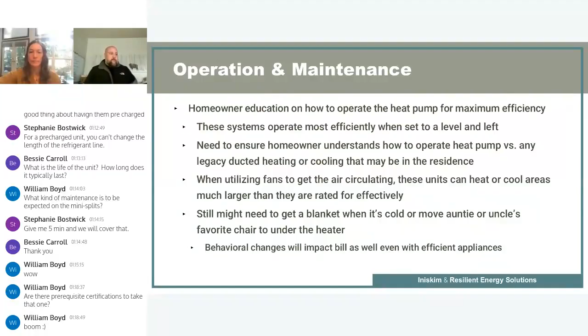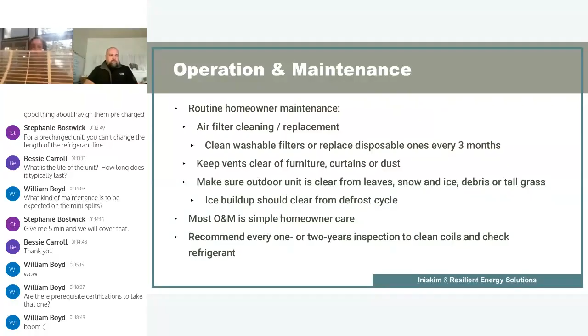Into the maintenance folks were asking about, it's pretty straightforward. The most routine thing you can do: nearly every head unit comes with a reusable mesh filter. I've got mine right here to show you what it looks like. It sits at the top of the head unit, and these are mesh filters in here. As air comes into the unit, it traps particulates on top of this mesh filter. You'll need a ladder since the head unit is mounted up high, but it just has a few tabs connecting it to the head unit, so it's easy to remove. You flip it over and spray it, either with a hose or your kitchen sink's spray mode, spraying from the inside out to get all the particulate off that came in with the air.